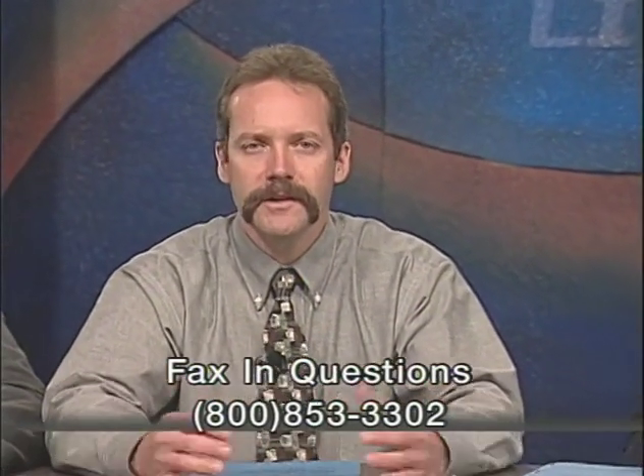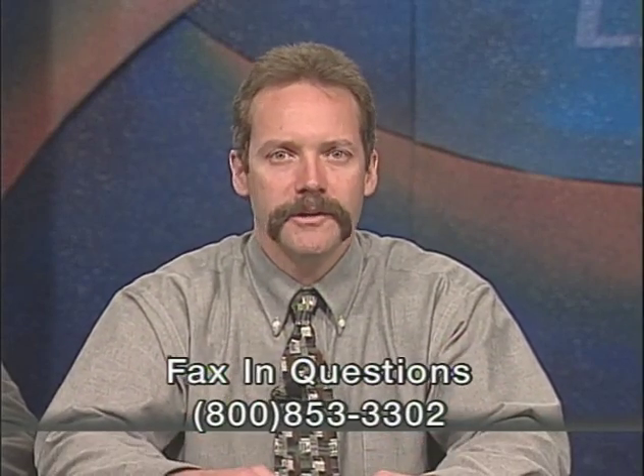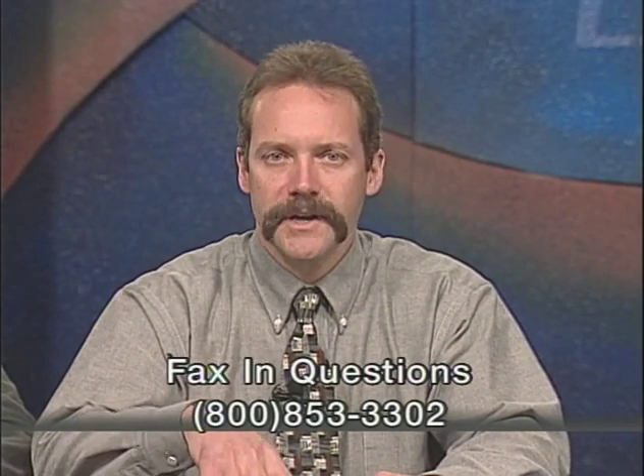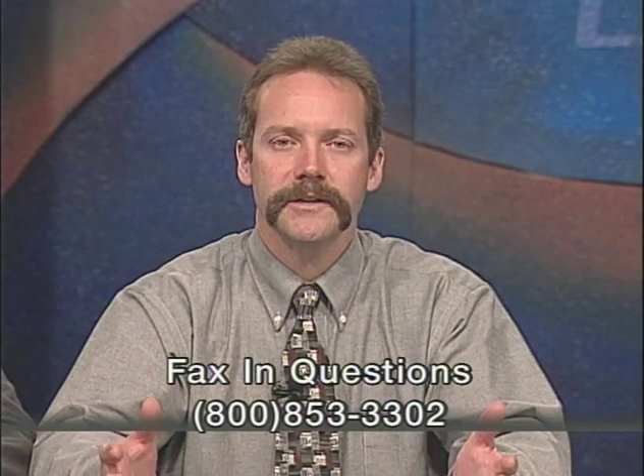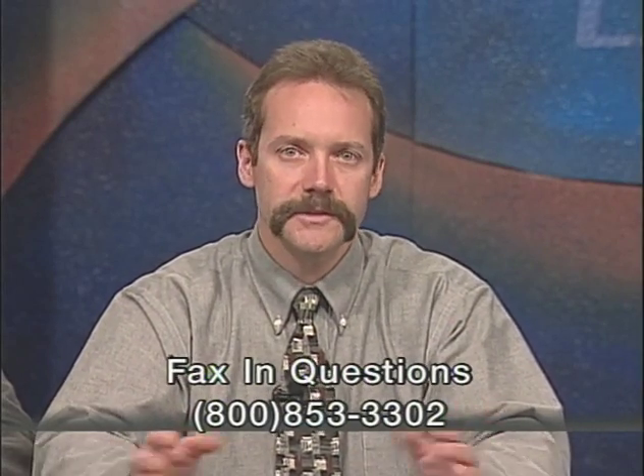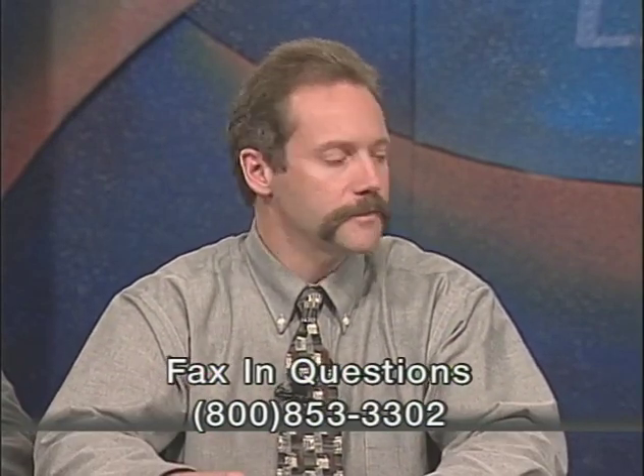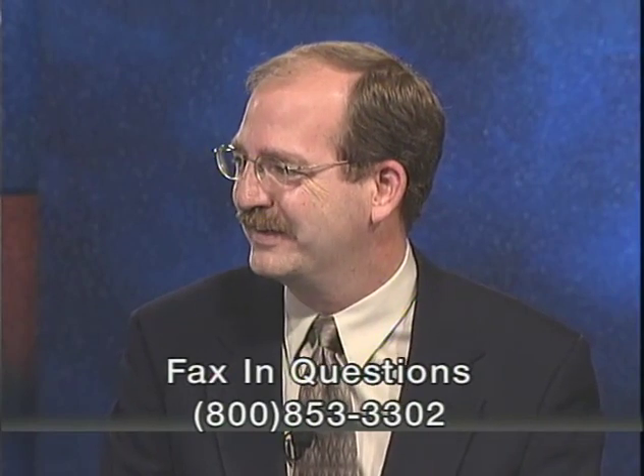Many people believe that they're providing for low classroom NC levels, NC25, and they don't look at the path, the breakout transmission, because they're just selecting the VAV boxes. Can you please address that issue? Sure, this is a great question. The sound in a room is the sum of all the sounds entering that room. So to focus on just one component like the diffusers leaves out everything else. The other thing about looking at just the diffuser is that the diffuser NC rating is based on some assumed room criteria. So if your room differs substantially from their assumptions, you won't even end up with an NC at that level, even if everything else isn't contributing. So we really need to look at it on a case-by-case basis using an analysis program. Definitely. Great, thanks a lot.